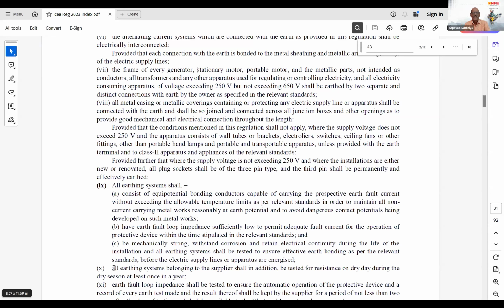The ultimate purpose is to provide safety on the LT side for safe and clear operation of automatic protective devices, and on the HT side to limit the fault current before the clearance of the fault. So these are the two things people should keep in mind. So with this, I think we can... Sir Hemant Sali, do you want to say anything about the Act and other provisions, before we go to the participants? We can take some questions.